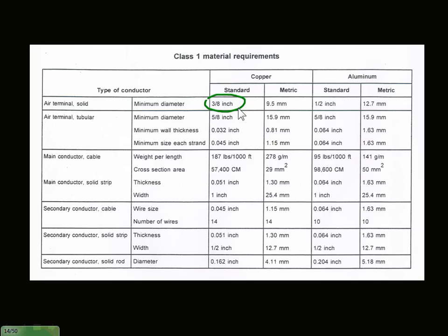So that's why we have a lightning protection conductor that's braided, and that's a lot bigger than your standard electrical wire. So as an electrician, you're probably familiar with number 6 wires, number 4 wires. This is probably equivalent to like a 1-aught, which is a lot bigger than your standard electrical wire. And the reason is it has so many volts that have to go through it.